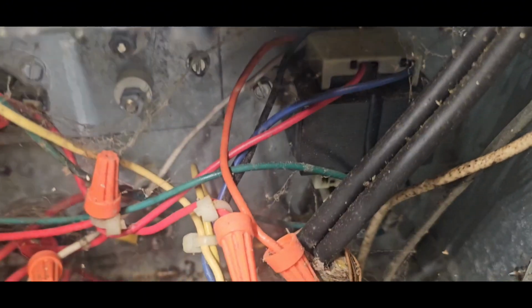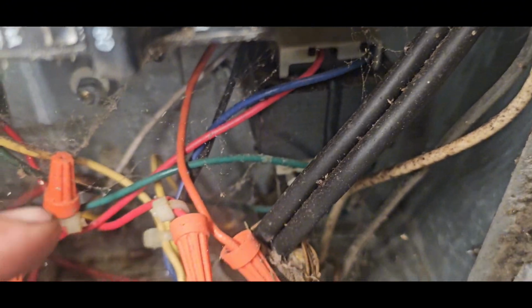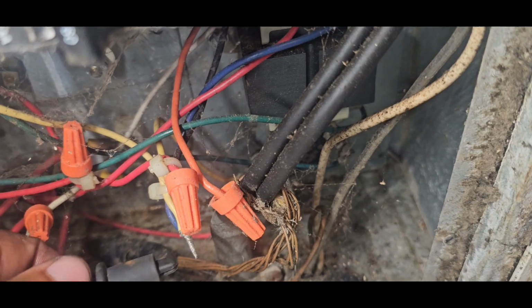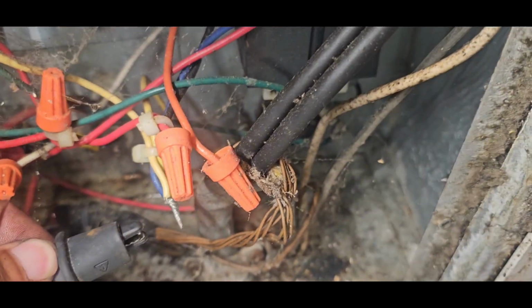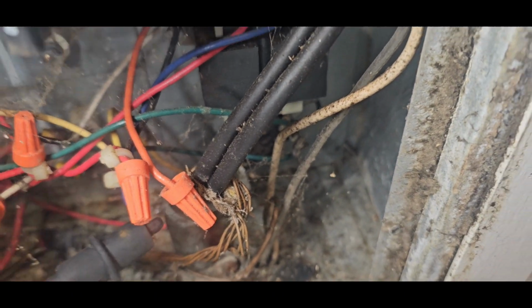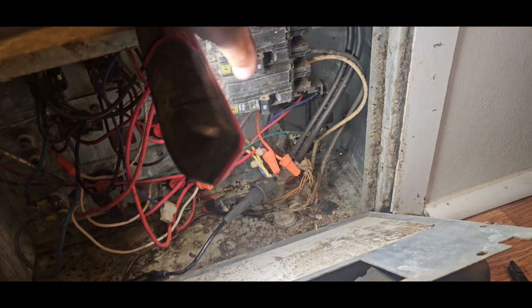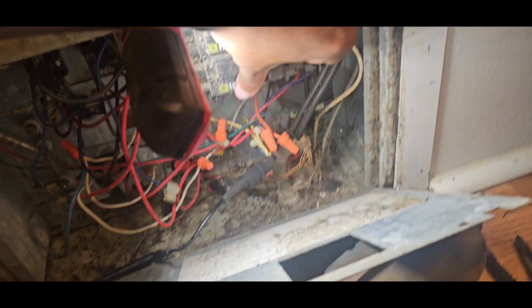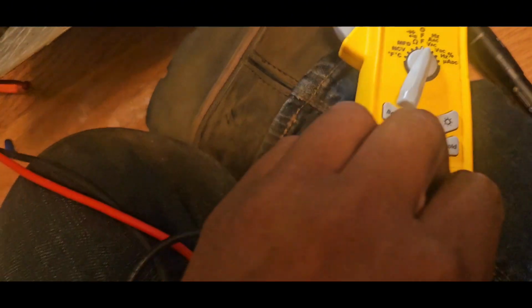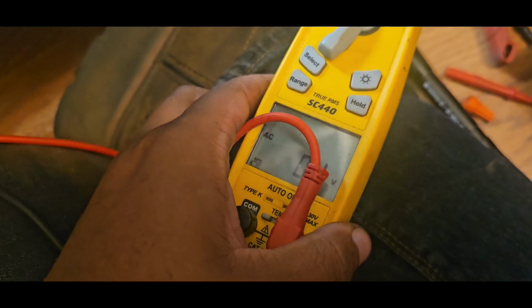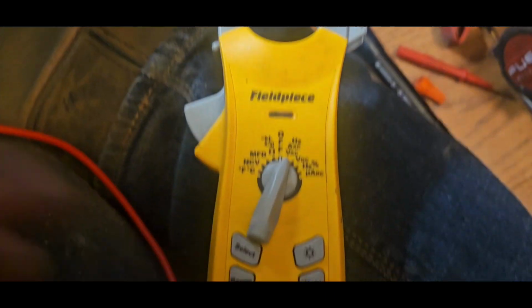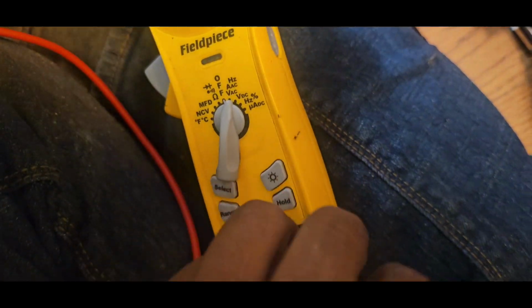If I can get the camera down here, I'm going straight off the contactor, following that blue down to where there was a wire nut here. Put my clamp there, turn everything on. I don't need the heat strips right now, but it seems like we don't have any power coming out of the transformer.